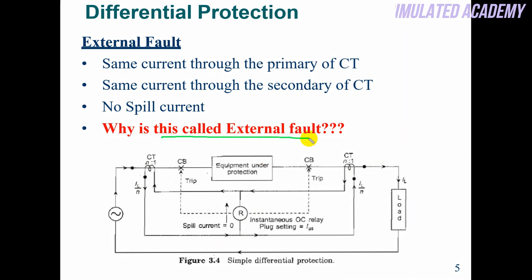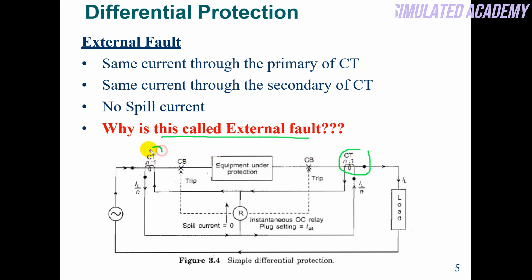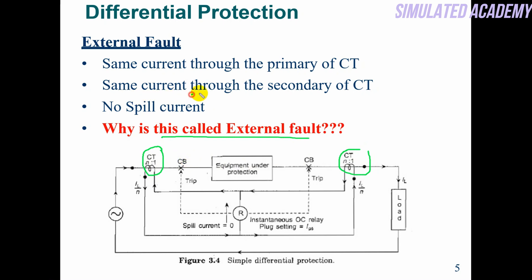The fault which occurs outside the CTs and PTs — beyond the zone — is called an external fault, also called a through fault. For example, if an external fault occurs, the fault current will pass through this CT and also through this CT. This means the spill current here will be zero. So for an external fault, this relay will not operate — same current through the primary of CT, same current through the secondary of CT, no spill current.